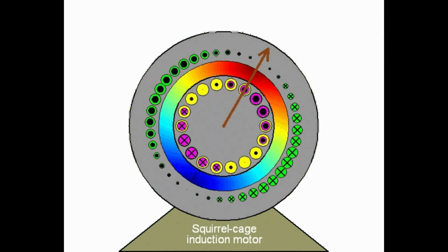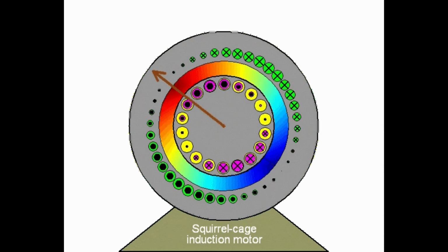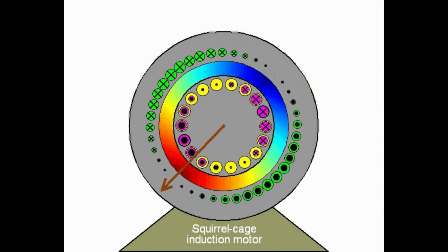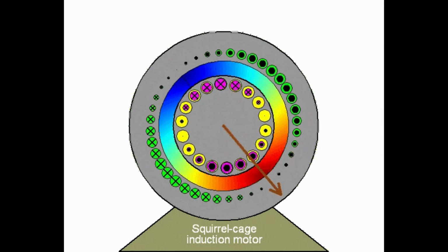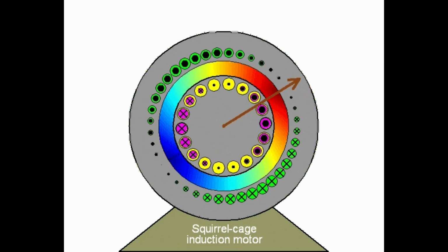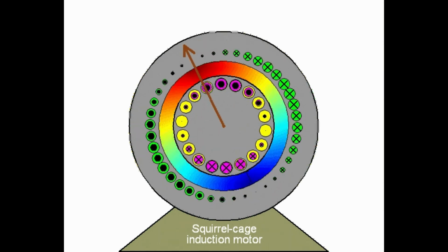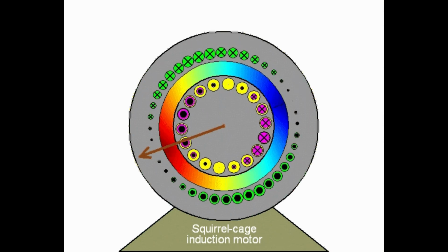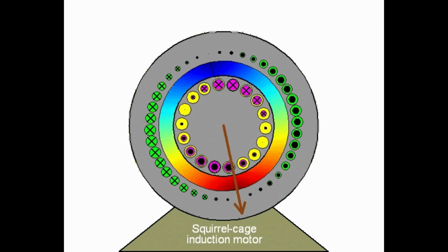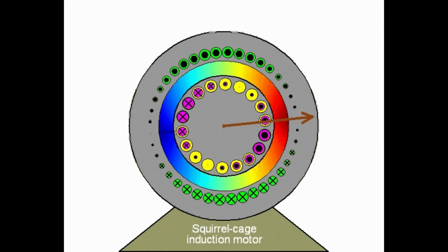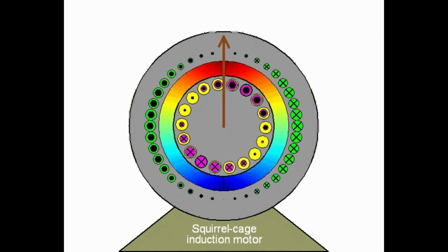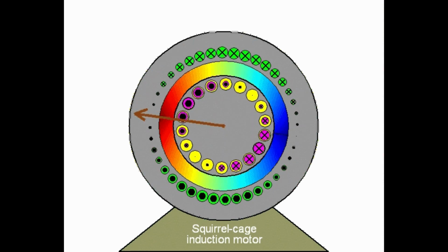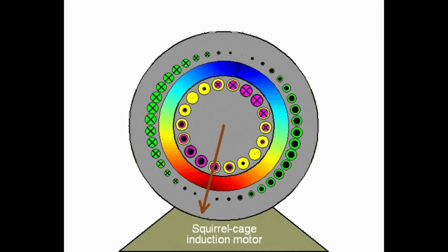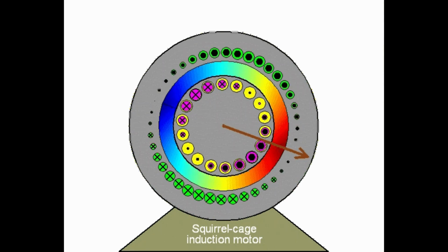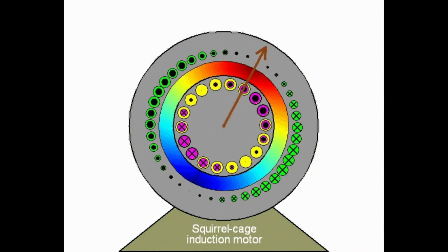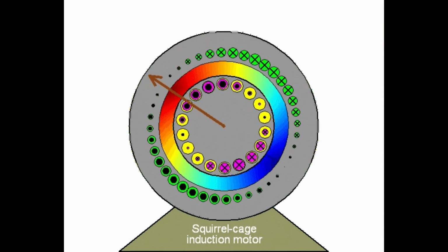The slip necessary to carry the full load depends on the characteristics of the motor. In general, the following situations are true. The higher the inrush current, the lower the slip at which the motor can carry the full load, and the higher the efficiency. Second, the lower the value of inrush current, the higher the slip at which the motor can carry the full load, and the lower the efficiency.